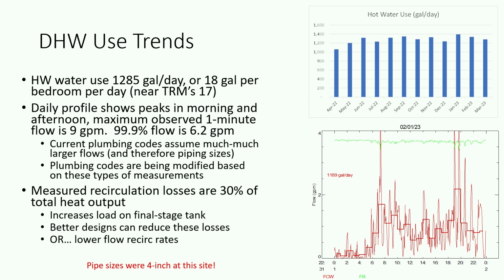So we are kind of affecting some of the recommendations for how to size piping and things like that. The other thing, like every hot water system, we could measure the recirculation losses. They were about 30% of the output from the heat pump. So the heat pump puts in energy, it comes out of the system as hot water use, but 30% of the energy that comes from the heat pump goes into recirculation losses.